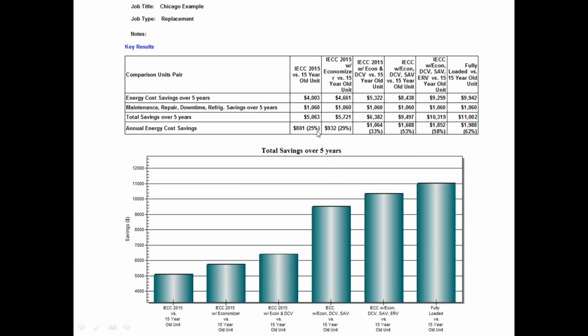Right. So just going from the existing unit to the code unit, 15-year-old unit to code unit is going to save me 25%, $800 in this example for Chicago. And the economizer, 932, right? With the DCV, a little bit more. With the DCV and staged air volume, that's the biggest jump from 33 to 53% right there. That's the biggest jump of adding things on.